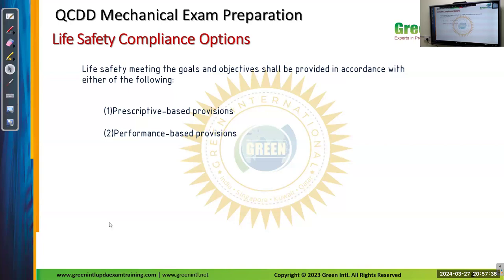So there are two main objectives or goals of life safety compliance. There are two different types: one is prescriptive based and one is performance based. Prescriptive based means we are studying NFPA and QCDD guidelines. It has a set of rules and regulations irrespective of the country or nation. If NFPA is regulated from the US, that is common to all, right? If you are constructing a building, with this much occupancy, you have to follow this much sprinkler systems or fire extinguishing systems. So it will have a set of rules. And even for QCDD guidelines, irrespective of whether you are building in Shamal or in Wakra, or constructing different types of buildings, it will have a set of rules and regulations based on previous experience, right?